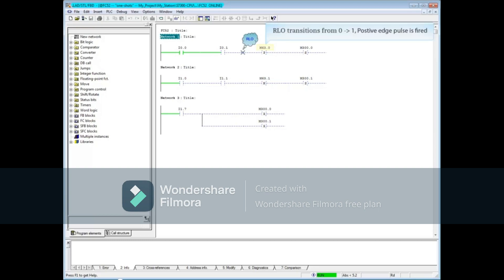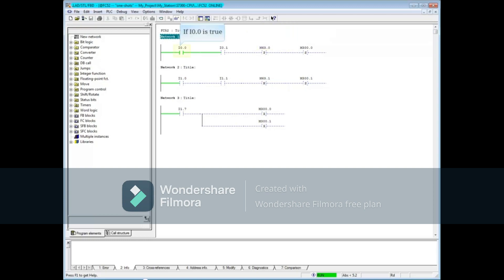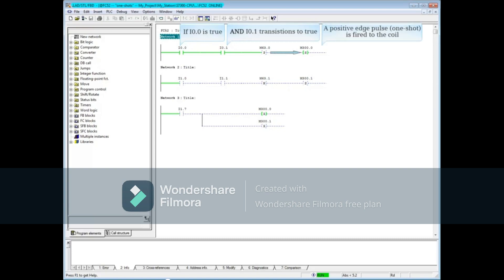When the RLO transitions from 0 to 1, a positive edge pulse or one-shot is fired through to the set coil M300.0. This means if I0.0 were true and I0.1 transitions to true, a positive edge pulse or one-shot is fired and the set coil M300.0 goes true.